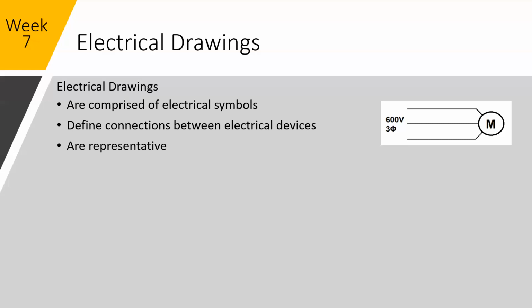These aren't mechanical drawings like you would get if you were a fabrication shop needing to actually manufacture the pump to assemble it. The electrical drawings that you're typically going to be seeing for PLC engineering work are going to be, you're going to have your 600 volt, you're supplying 600 volt to a motor. The motor, you might have your horsepower or kilowatt rating. And then you'll have your control circuits. It would be far more detailed drawings that would get down to individual connection points.